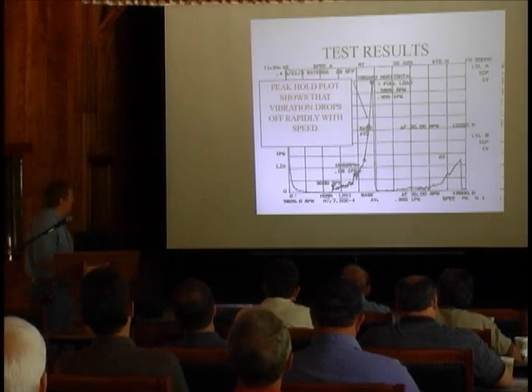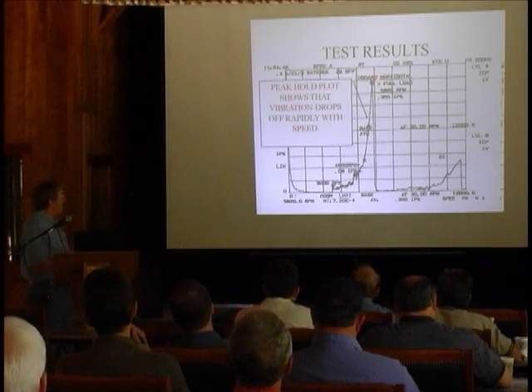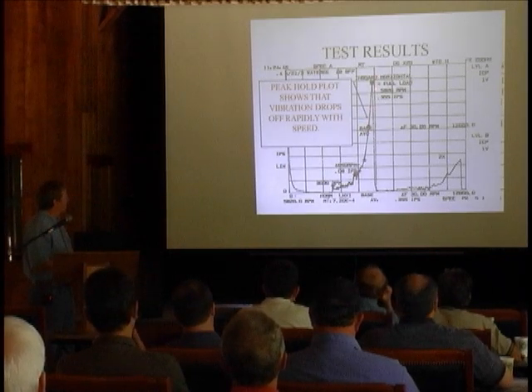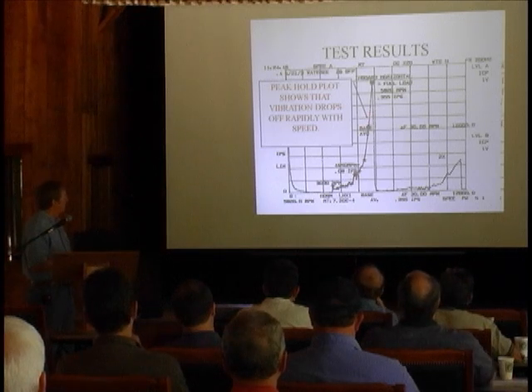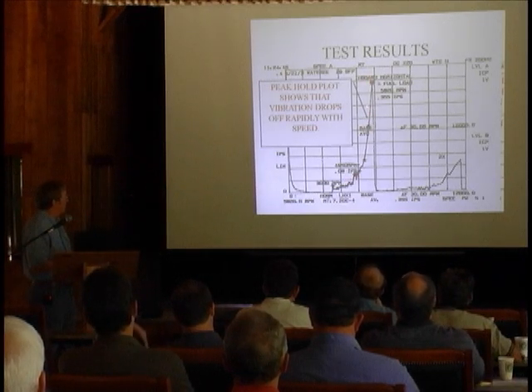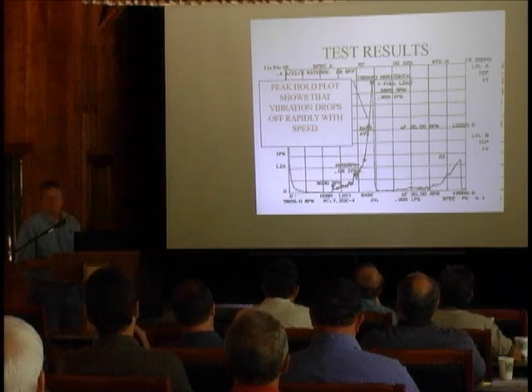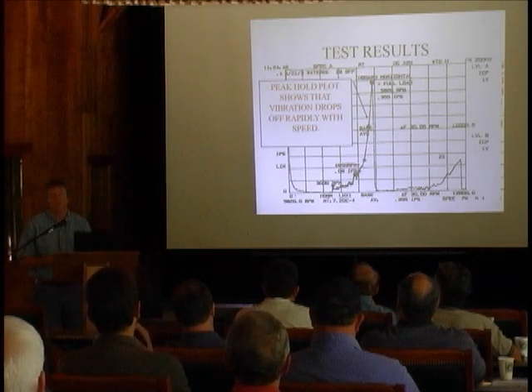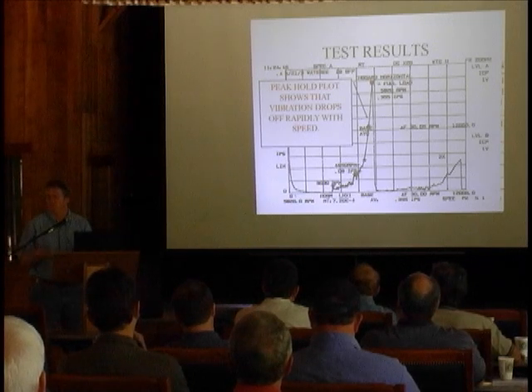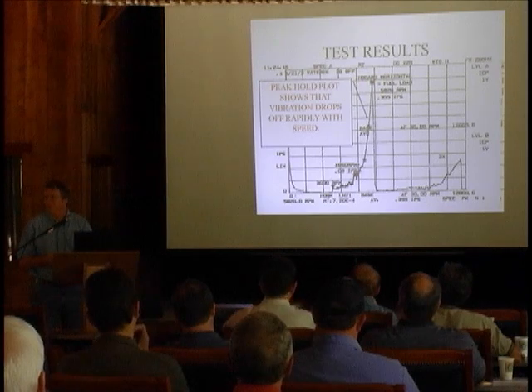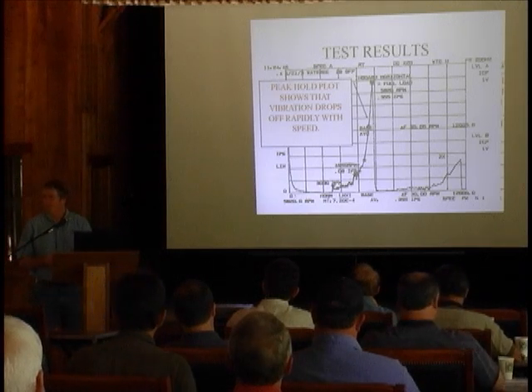I did a peak hold plot of it, and you can see right here, when I bring my RPM down, look how the vibration drops. So what are we operating near? What would you be operating near if the vibration changes a lot when you come off speed? Resonance, natural frequency. How come it wasn't there to begin with? There wasn't a natural frequency there when we put the pump back together.